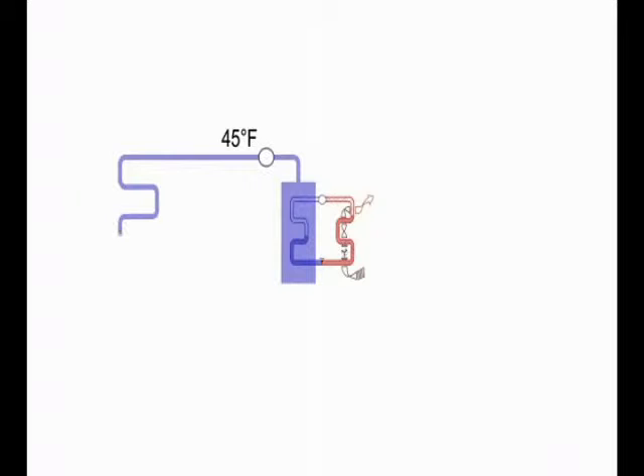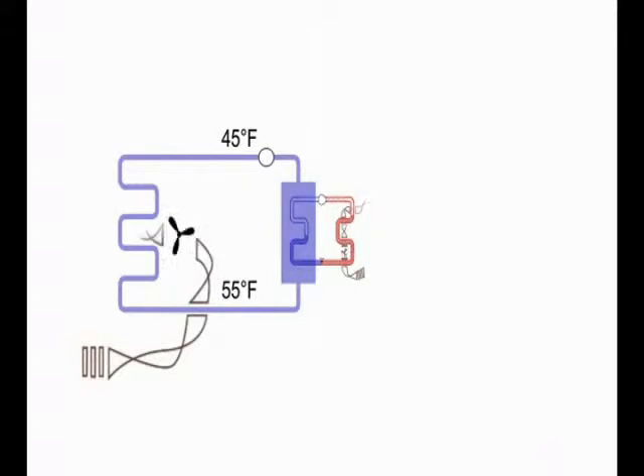In this regime, pumps carry water chilled on the evaporator side, which is to say the cold side, of the compression refrigeration loop, to sometimes distant air handling units. The air handling unit then blows air across coils of chilled water, rather than coils of chilled coolant as we saw in previous examples, thereby cooling 70-degree return air to 50 degrees for distribution through ducts.